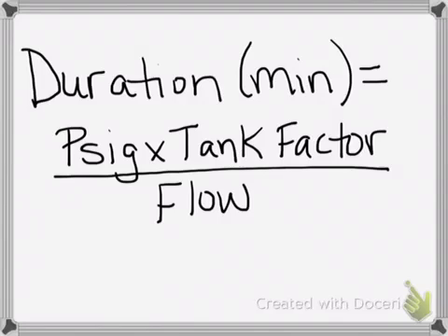This is the equation. The duration that the tank will last in minutes equals the PSIG, which is the pounds per square inch gauge. This is the amount of pressure in the tank and can be found with the pressure gauge. Take that and multiply the tank duration factor we just discussed. Divide by the flow that the patient is receiving in liters per minute.